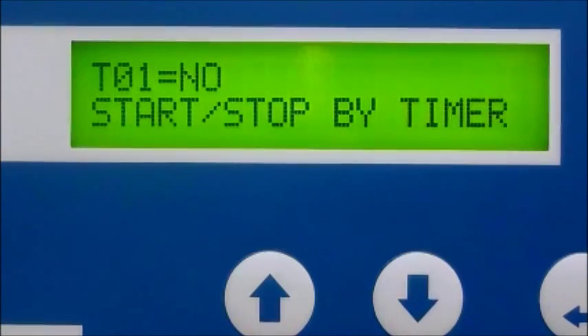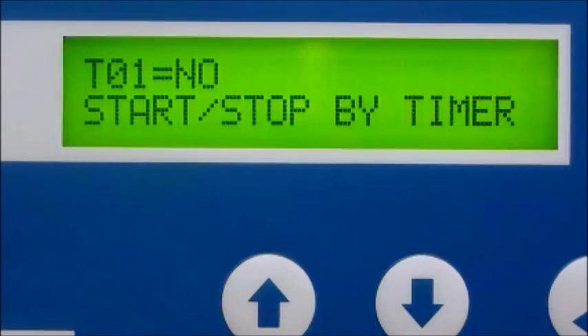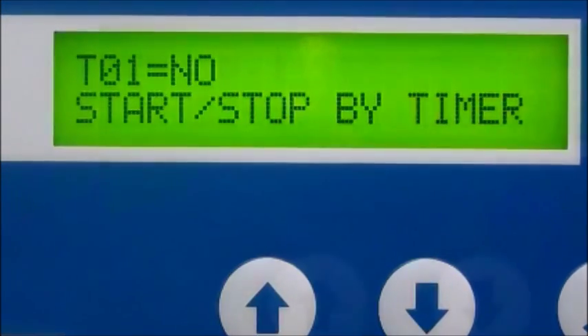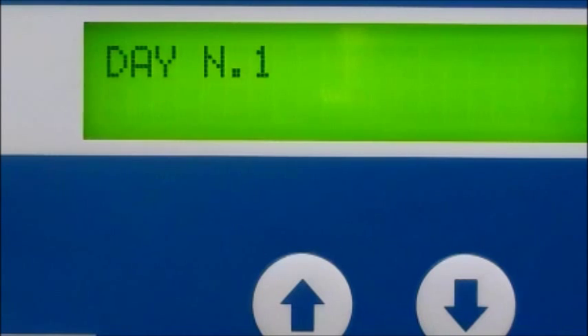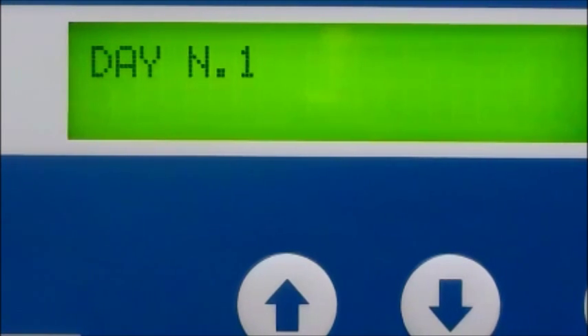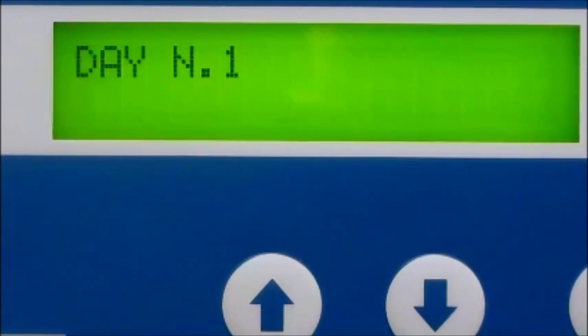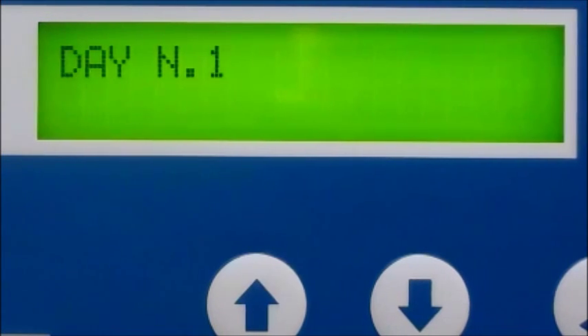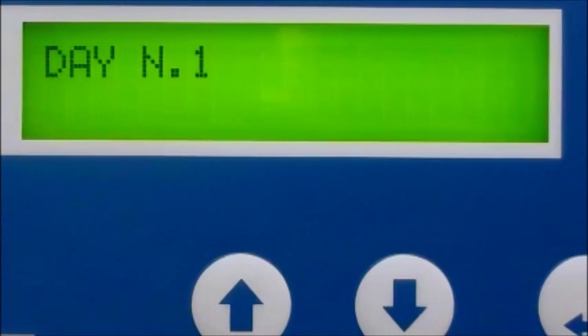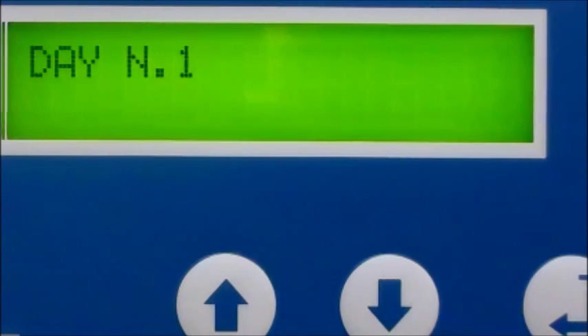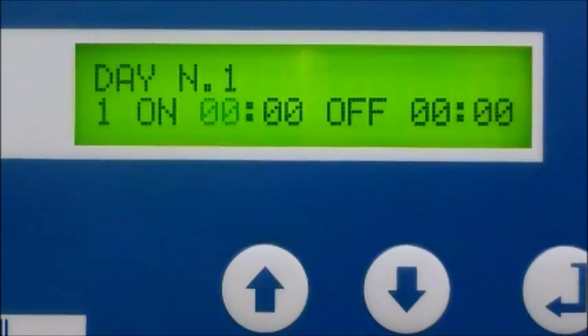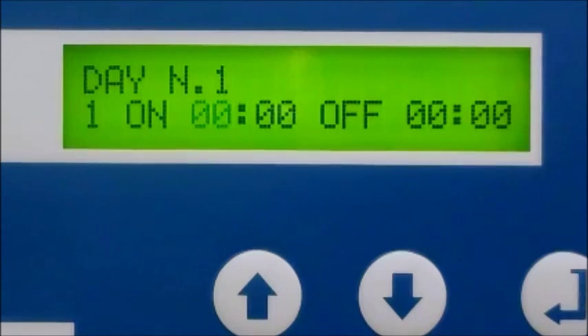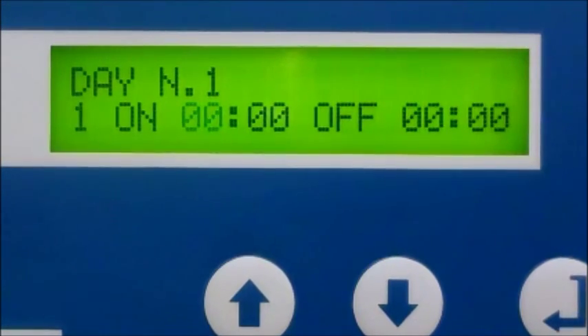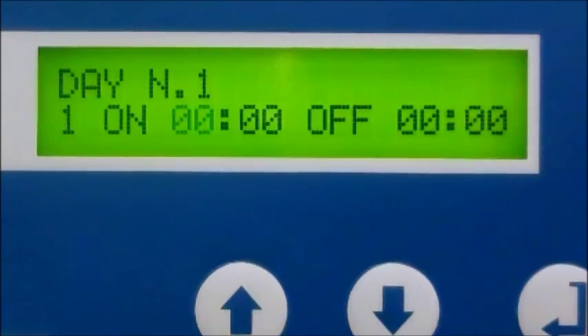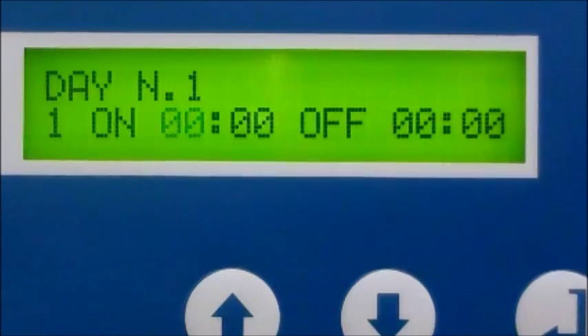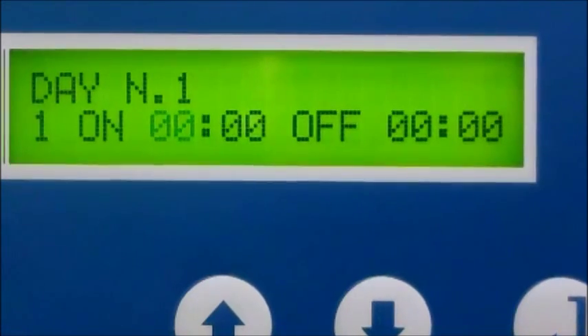The programmable auto start auto stop feature triggers the compressor to automatically start and stop once, twice, or 3 times per day and up to 7 days per week if required. This function is programmed through the built-in clock and PLC calendar. Basically, if first shift begins at 7 a.m. and ends at 4 p.m., you can program the PLC to auto start at 6:55 a.m. and auto stop at 4:05 p.m. Let's face it, just one less thing to worry about in your busy day.